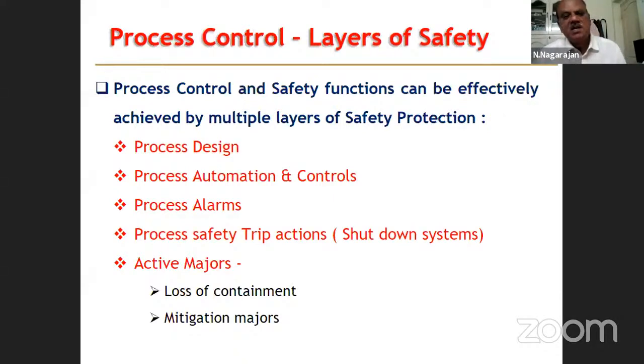Then the process automation and controls, the process parameters, various operating parameters are being measured, monitored, and controlled in an automatic system. Then process alarms. During the process operation, if any of the parameters exceed, there will be an alarm. First, there will be an alarm to alert the operator to take care of the system upsets. But if the operator fails or if there is no immediate solution available, then it goes to the trip system, process safety trip. It will trip the plant, or it will trip the equipment, or it will trip the system, a particular system. So this is a safety measure from the operation point of view.